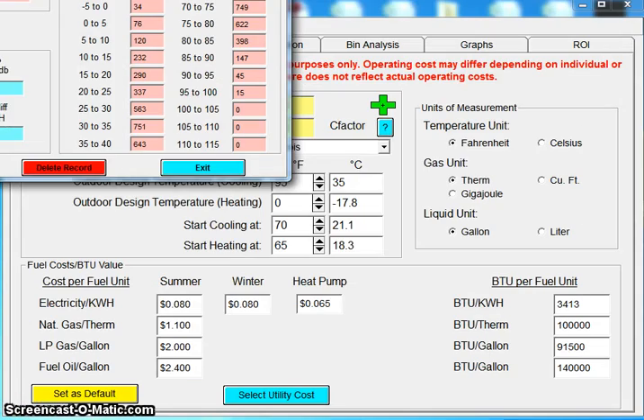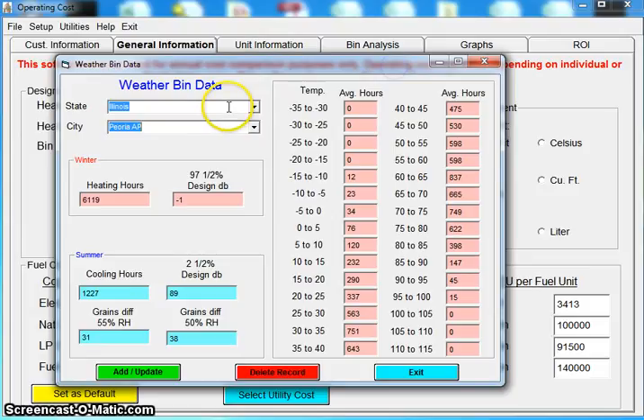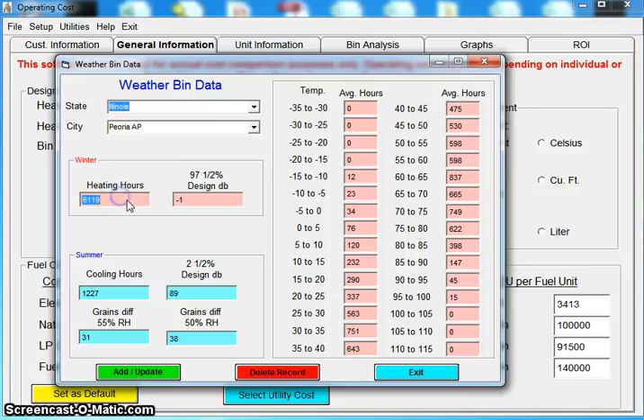Now I'm going to open up this screen. We have weather bin data pre-loaded in here. This is an average of the last 10 years weather data. And you can see here in Illinois we have 6,119 heating hours and close to 1,200 cooling hours.